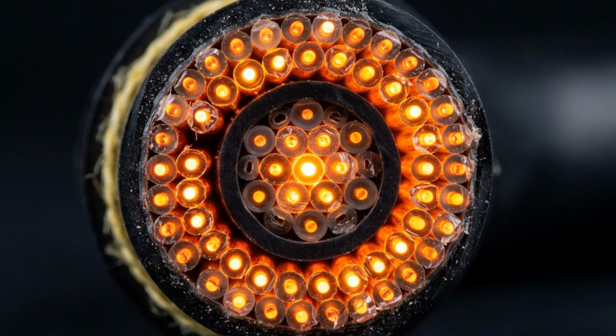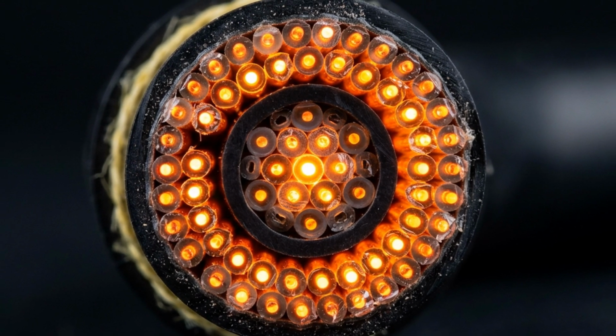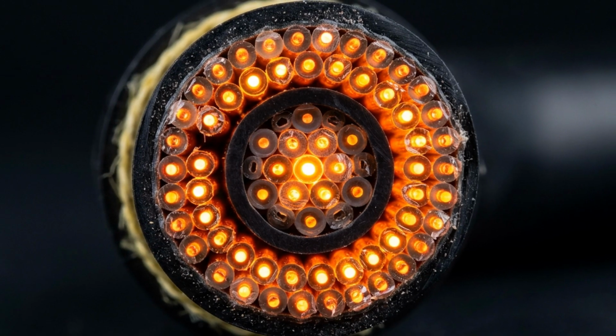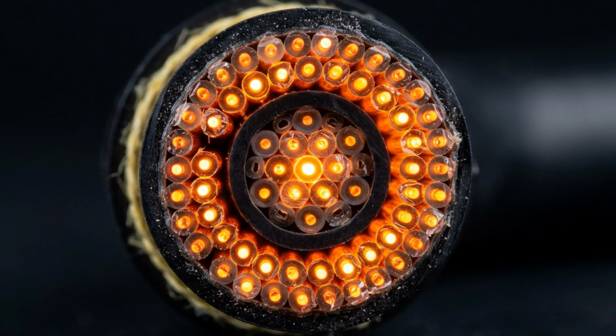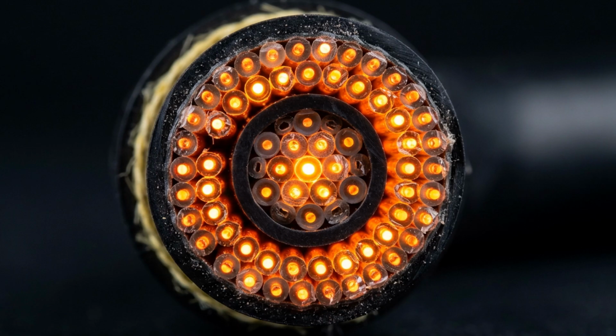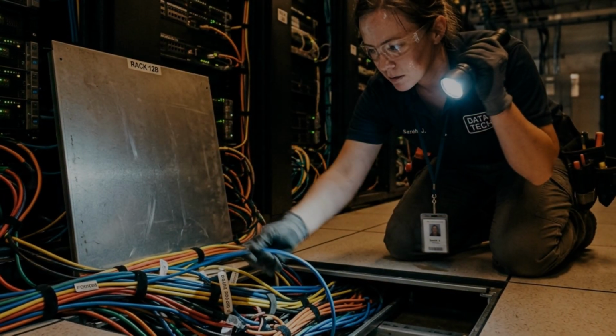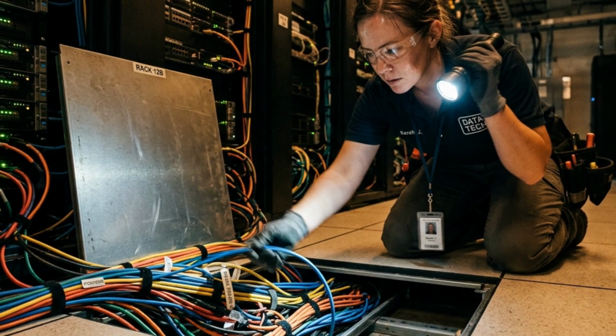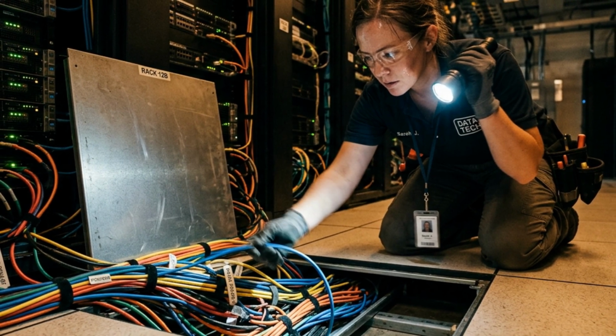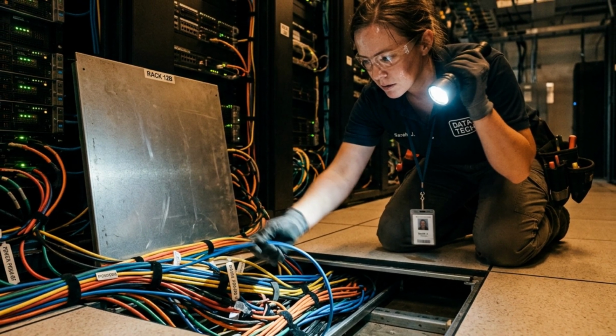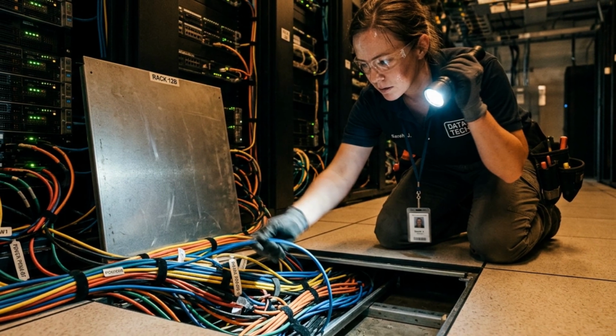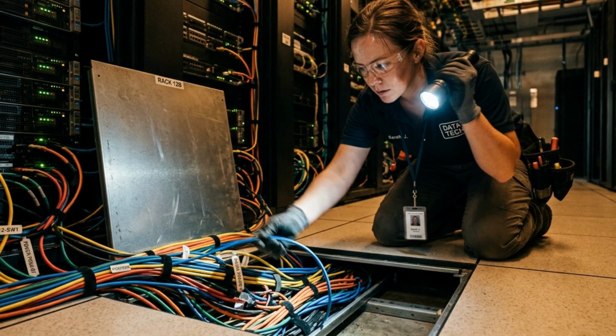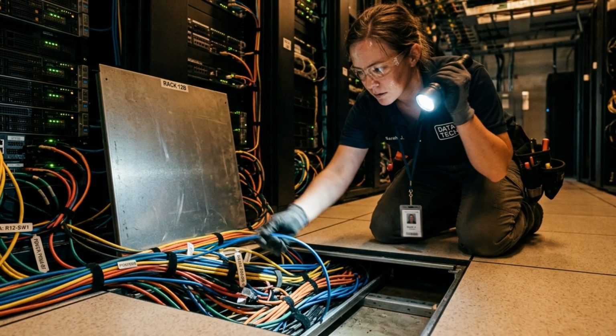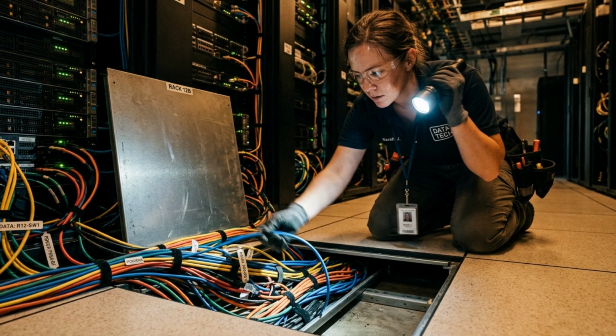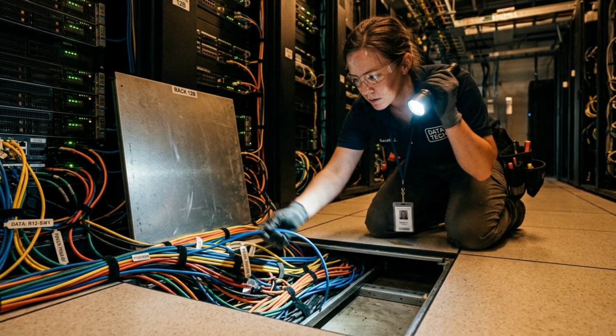The cooling systems in a hyperscale AI facility are not peripheral equipment, they are central infrastructure, consuming roughly 30 to 40% of the facility's total power budget. Engineers track a metric called power usage effectiveness, comparing total facility power to the power used by the computing equipment itself. The best facilities are approaching a ratio of 1.1 or even 1.05, meaning nearly all of the electricity consumed goes directly into computation. This is the most impressive part of the entire operation, and it happens invisibly, thousands of times per second.